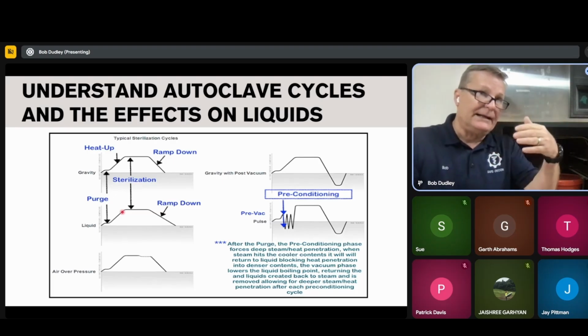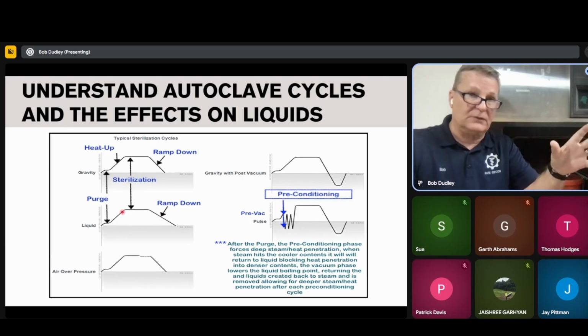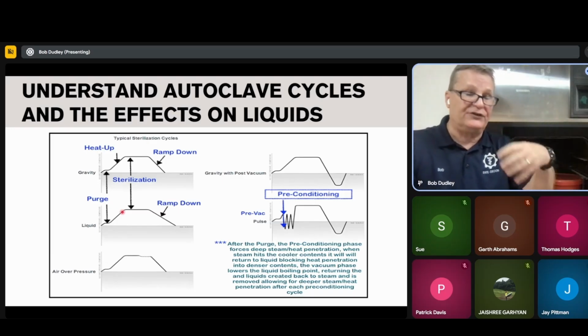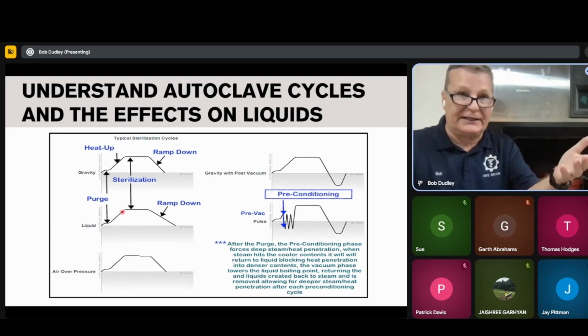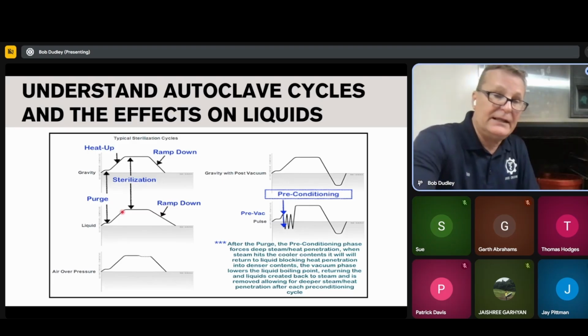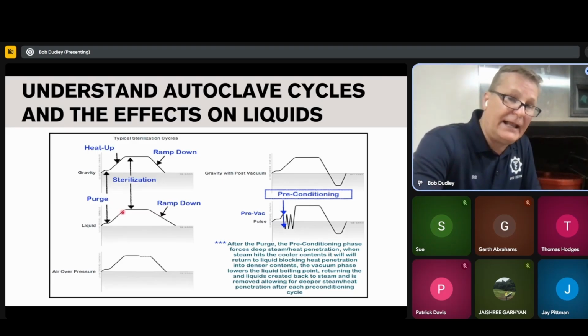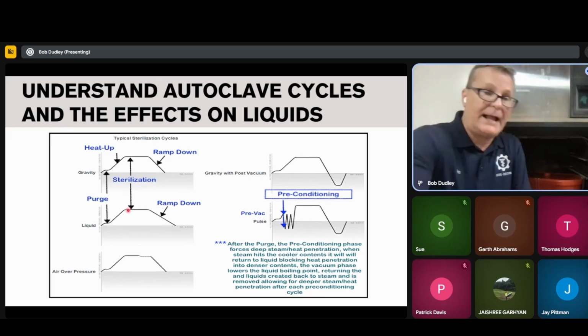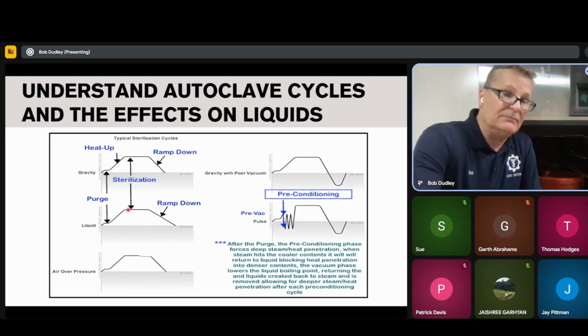If the drop rate is at, and some of them are preset for 1.5, 2 degrees over 30 seconds or potentially a minute. If we do achieve that, then you get the final push, and then it'll bring it up to sterilization. Now, once it gets to sterilization on these two, it's going to go back and recheck everything. And they do this just to make sure that the autoclave is working correctly.